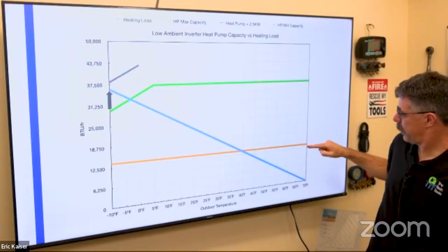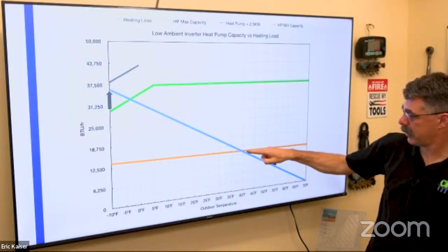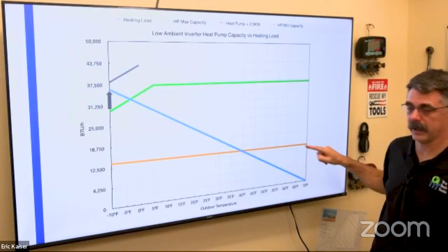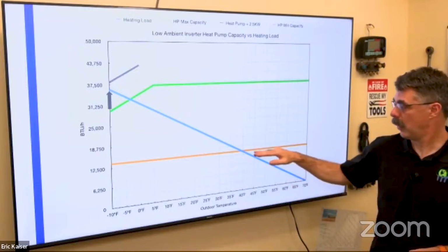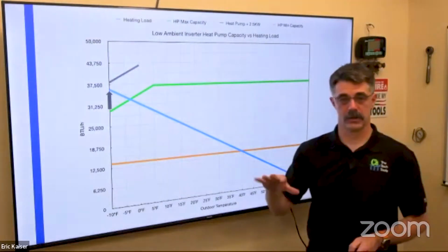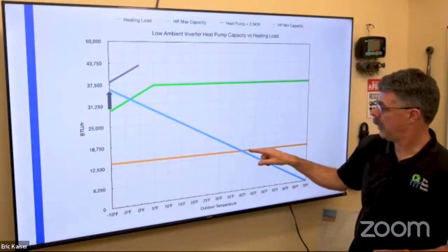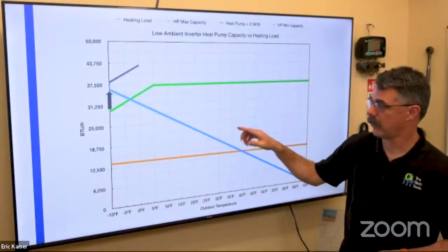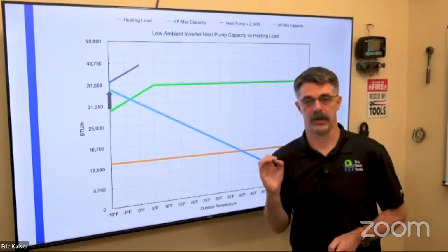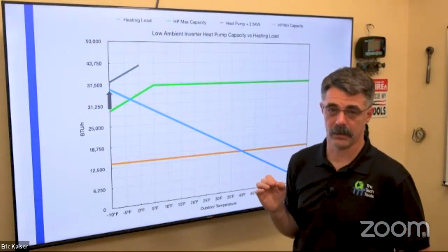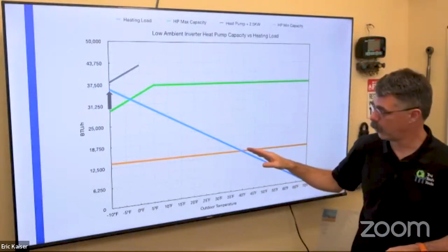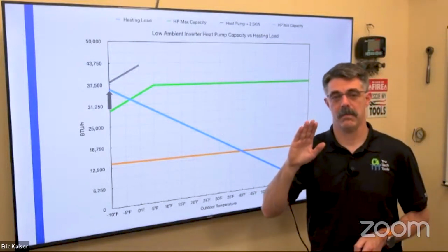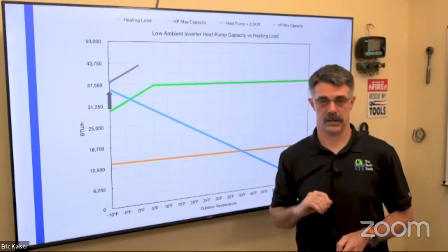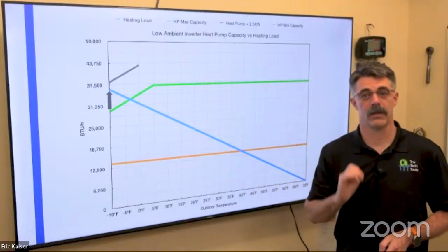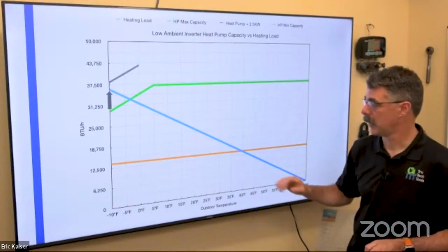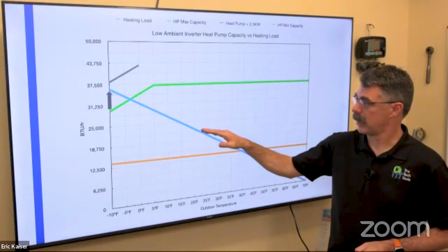So all the way down to about 40 degrees, that heat pump's going to be cycling off and on periodically. Once that outdoor temperature hits 40-ish degrees, that heat pump should just ramp up slowly and run almost 100% of the time. It might cycle off once in a while, but it should run almost 100% of the time at the minimum speed necessary to condition that house. And that's the way they're designed to operate. Okay. So once we get down here, it should be running 100% of the time.